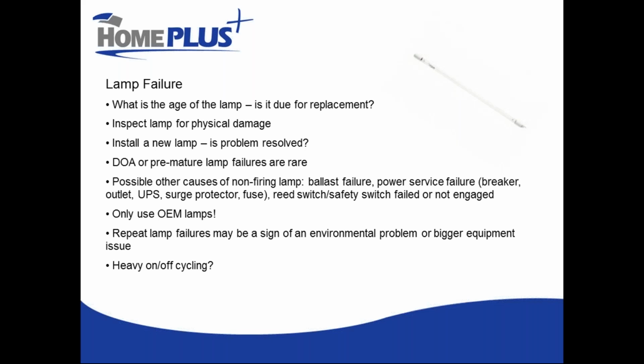But in our experience, they cause a great deal of problems. The UV output is rarely equivalent. They rarely last as long, and in extreme cases, they actually cause equipment damage. We've seen even fires caused by poor fitting lamp pins and that sort of thing. I'm aware of a small water system on Shuswap Lake that was using non-OEM lamps and caused about $15,000 in damage to their UV equipment doing so. So be very careful where you're buying your lamps and make sure they're genuine OEM lamps so that you know exactly what you're getting.